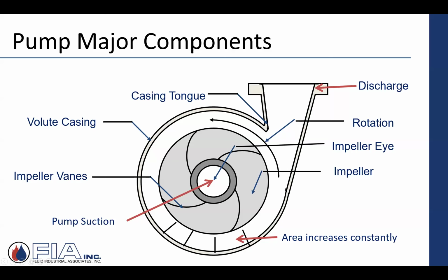This is the direction. You can see the arrow pointing to rotation. So it's moving in this direction, counterclockwise, I guess we could say. And as it's spinning, those vanes are taking that water and adding velocity. And the velocity is at its absolute peak right at the tip of the periphery of the vanes at the edge of the impeller. And then the water is kind of gathered, if you will, in that volute, and then eventually discharges out, if you will.